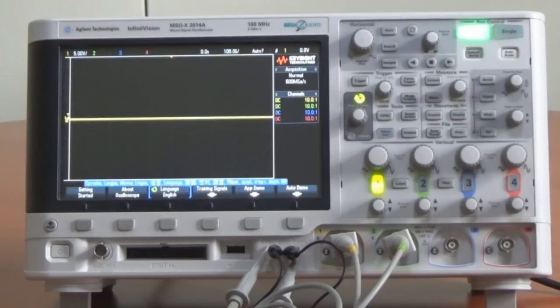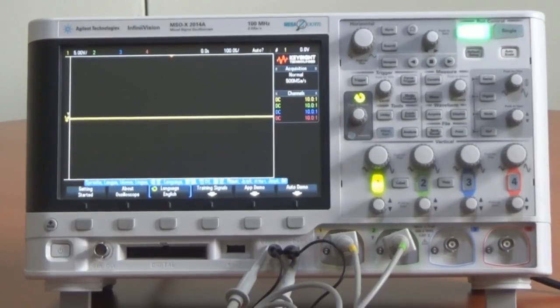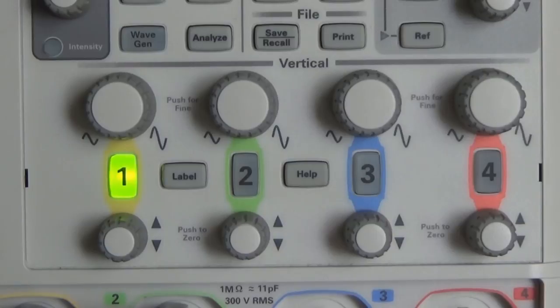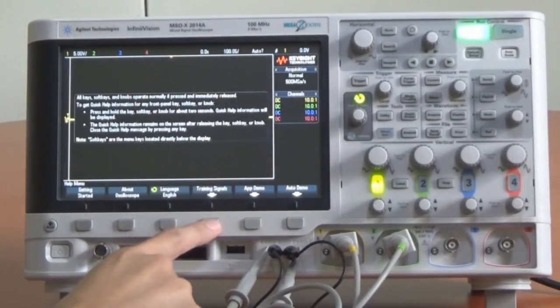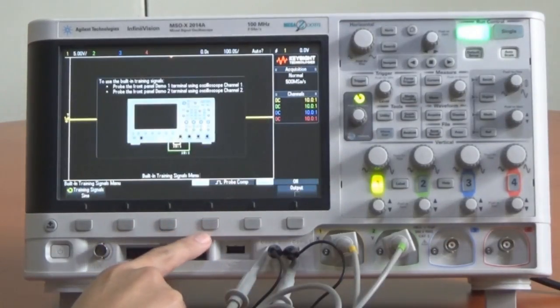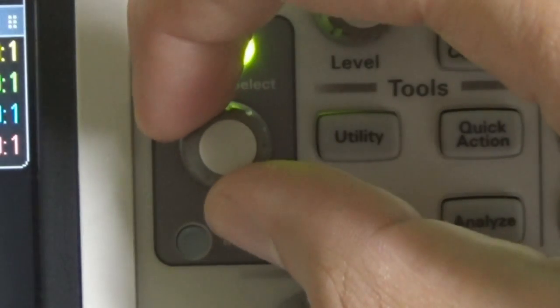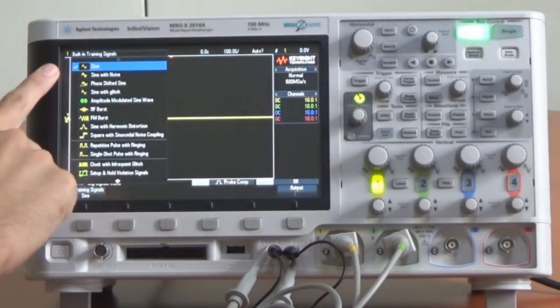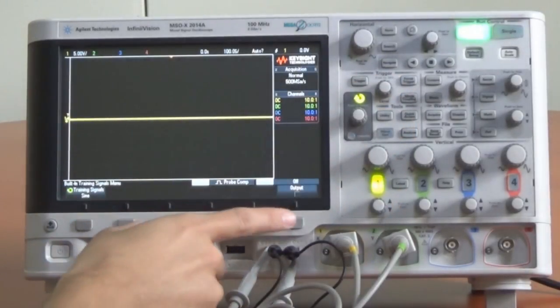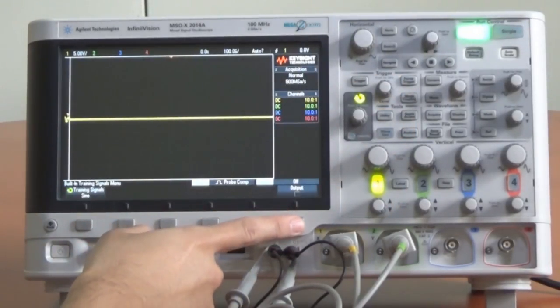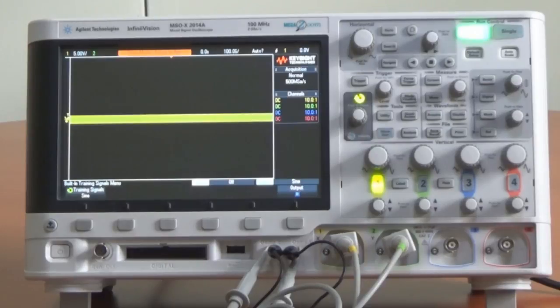Presionamos la tecla Help del panel frontal que está cerca de los controles verticales del canal 2. Luego presionamos la tecla programable Training Signals debajo de la pantalla del osciloscopio. Con la perilla Entry seleccione la señal Sine, la cual se encuentra en la parte superior de la lista. Luego presione la tecla programable Output para encenderla. A continuación debería encontrar una onda sinusoidal en el terminal Demo 1, pero todavía no se le reconoce con los factores de escala predeterminados del osciloscopio.